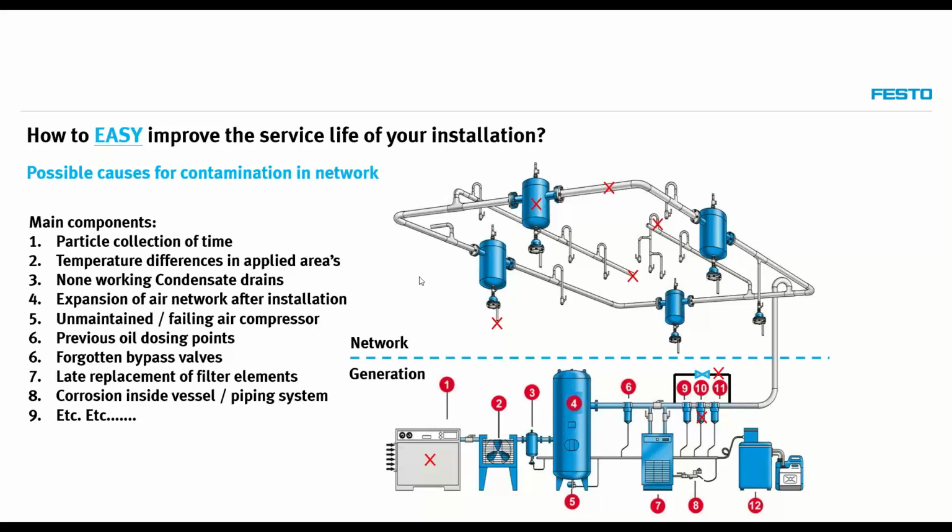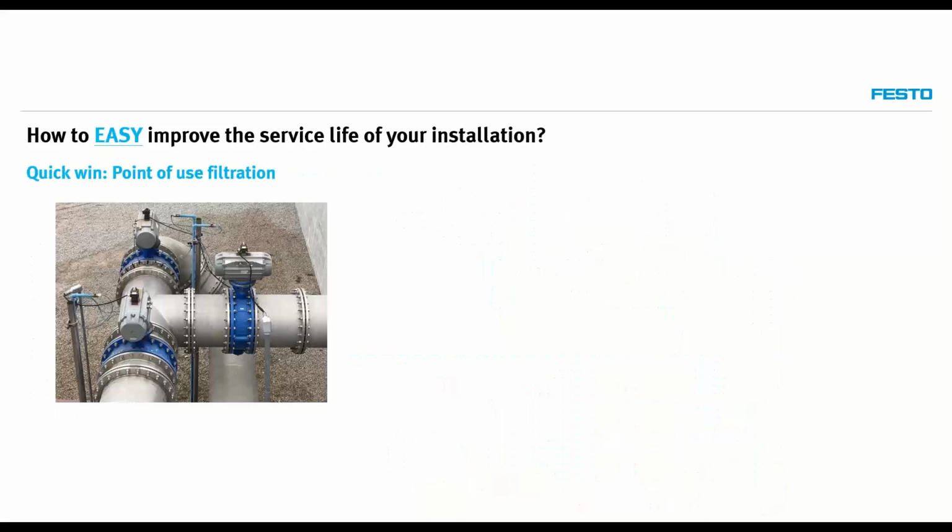So if we go to the next slide. The air supply is coming from the field with individual tubes, and there's a direct connection with the compressor. So the actuators have no type of filtration protection.